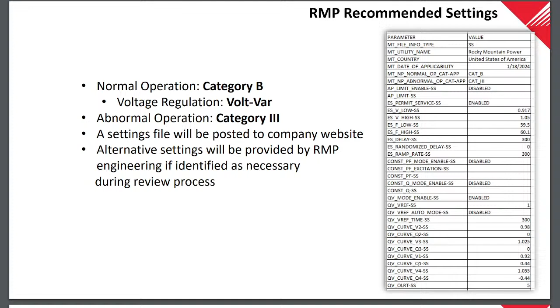Yes, it would be based on what we come up with for settings. On the next slide we'll show our volt-var settings, which will give you an idea, because there's a graph. There's a similar graph for volt-watt mode. Both modes work by measuring voltage and trying to adjust it by varying the inverter output, either watts or vars. We set it according to a graph, and that graph determines, depending on the voltage, how much watts are output. You'll be able to see in the setting graph what that looks like.